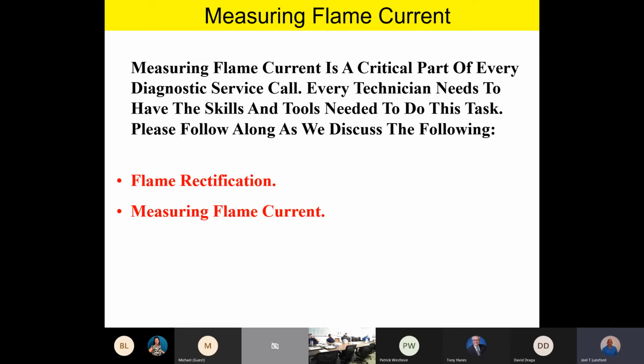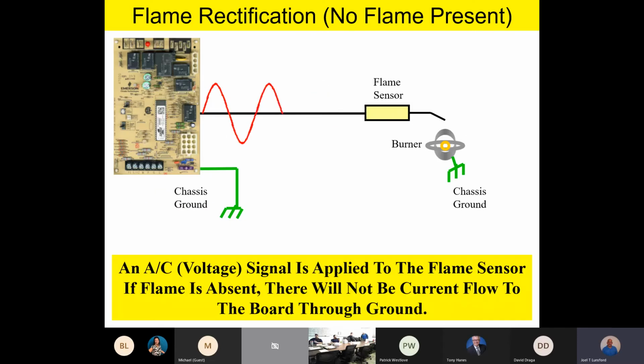This is something I believe every technician needs to have the skills and the tools to do. To measure flame current, as we found out a little bit ago on that flame current pad, all we need is a DC voltmeter. But before we get into reading flame current and some of those specifics, let's talk a little bit about the science of flame rectification, and then we'll talk about measuring flame current. Flame rectification is basically a science where we provide AC voltage to our flame sensor all the time.